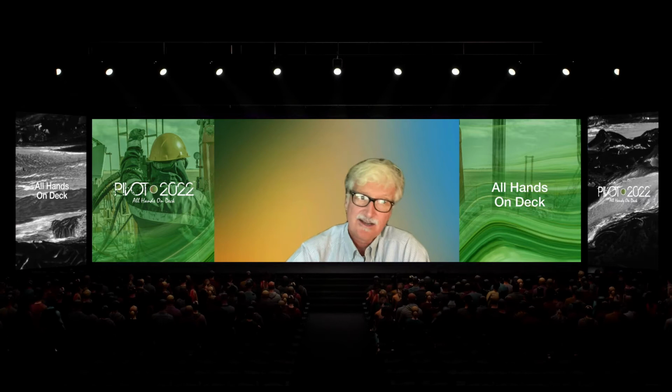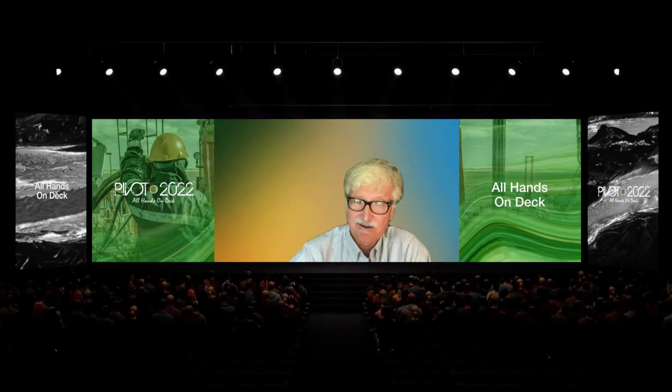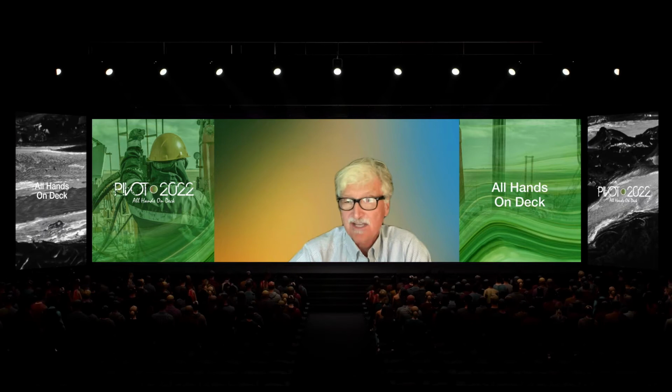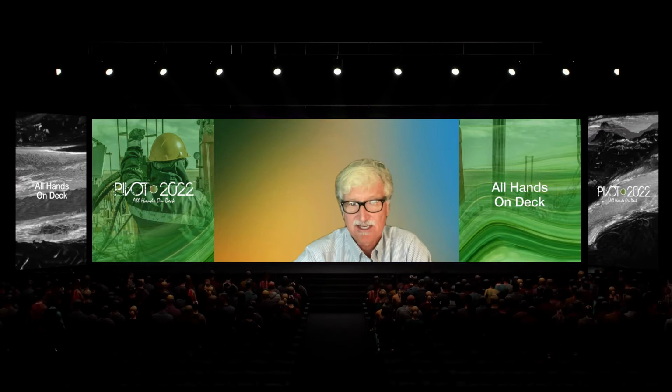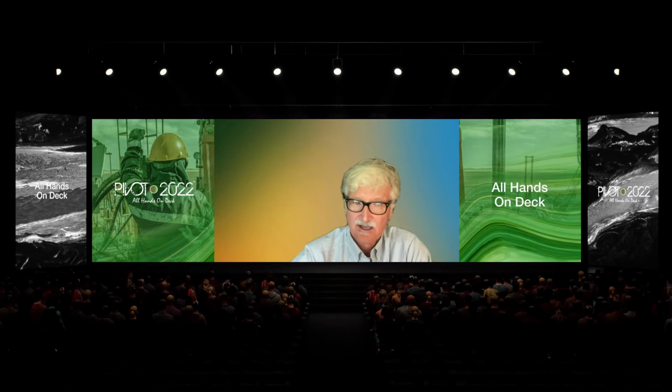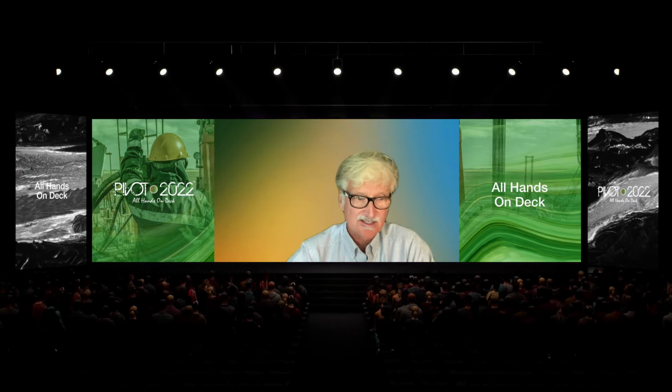So what is superhot rock? Just for everyone in the audience, at 400 degrees Celsius, water is in a supercritical state. What that means is it's more fluid and it carries more heat. And by preliminary estimates and measurements, much more energy per well, which gives superhot rock the potential to be competitive. And that's really the key thing right there. With successful advances in drilling and reservoir creation, well completion, it has the potential to be widely distributed. It's zero carbon, it's firm power, and it's high energy density. In other words, that is small footprint for very large amount of energy.